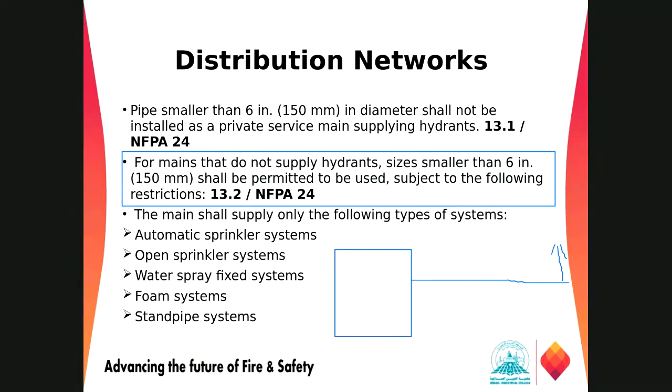But in no case for the fire hydrant do we go below 6 inch, as per NFPA 24, because at that time we have higher friction losses when the hydrant is working at full capacity, and we may encounter more pressure losses due to those frictions.